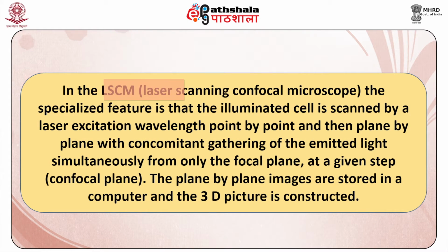In the LSCM, which is the laser scanning confocal microscope, the specialized feature is that the illuminated cell is scanned by a laser excitation wavelength point by point and then plane by plane, with concomitant gathering of the emitted light simultaneously from only the focal plane at a given step, the confocal plane. The plane by plane images are stored in a computer and the 3D image is constructed.